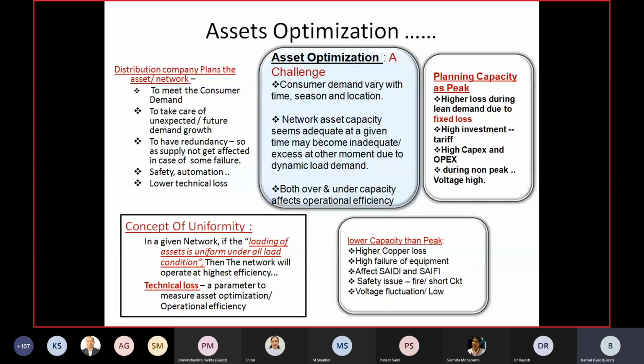Demand varies continuously. If I plan everything for the peak, like in Delhi, where as I said my peak is 3200, and if I plan keeping N-1, that means something like 7000 megawatt for 3200, my average loading or load factor is 50% of the peak, because in winter the demand becomes almost 15 to 20% of the peak. So my average load for the year will be half of the peak. That means for 3200, if I plan 7000, my average load is 1600. So for 1600, I have planned 7000. In winter, it will be 800. For 800, I have planned 7000. Imagine how inefficient my circuit will be, and how much more technical loss I have because of the fixed technical losses of the assets. So it is very important to plan with a concept of uniformity, so that the loading of assets remains the same throughout, as far as possible near the average value and the desired value.